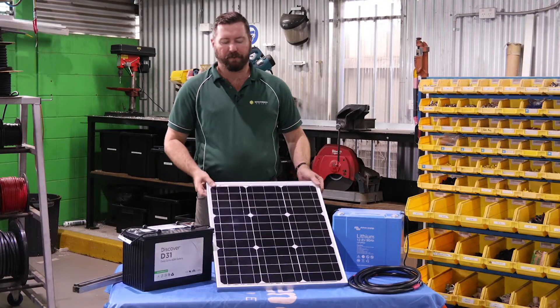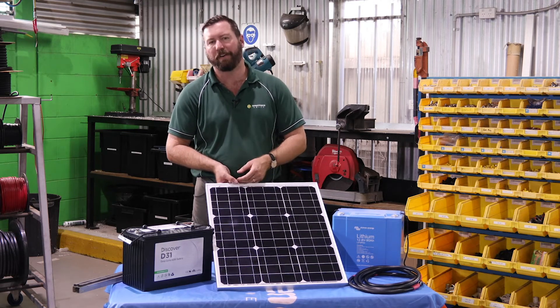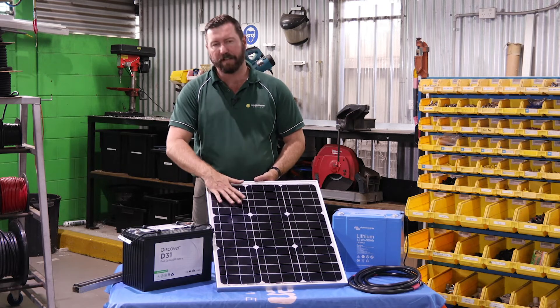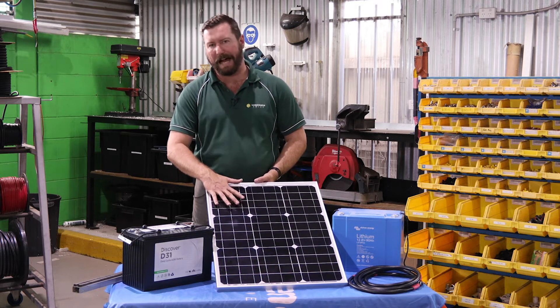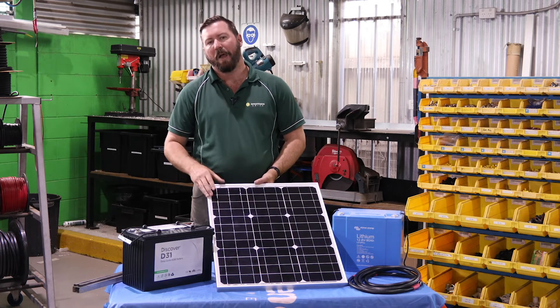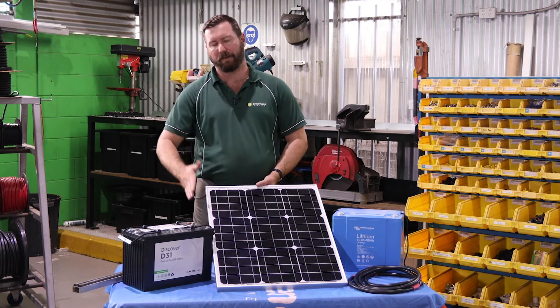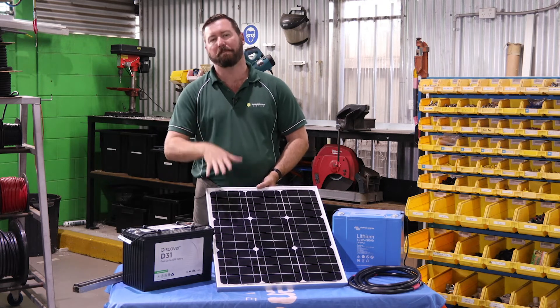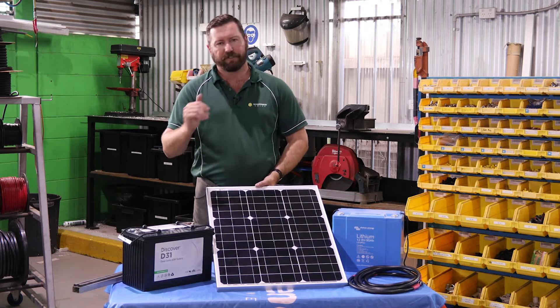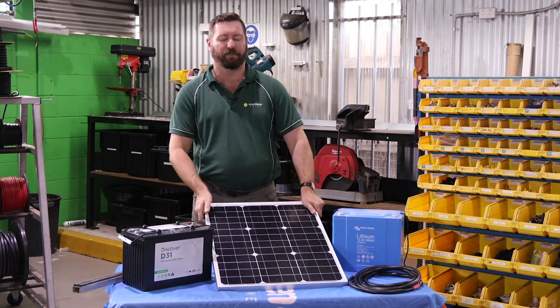If this was a 140–150 watt panel able to produce seven amps at 12 volts in full sun, even some shadowing in the corner with a hard shadow line will drop its output to one to one-and-a-half amps — a dramatic reduction. Hard shadow lines from structure, supports, rails around roofs, shovels, or whatever you've got up there — if it's shading that panel, you're going to dramatically reduce its output.